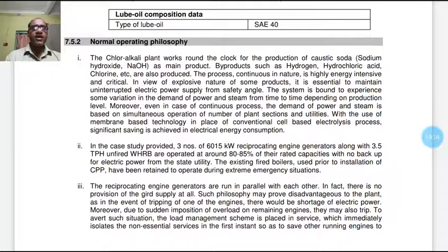The existing fired boiler used prior to installation of CPP has been retained to operate during extreme emergency situations. The reciprocating engine generators are run in parallel to each other. In fact, there is no provision of grid supply at all. Such philosophy may prove disadvantageous to the plant, as in the event of tripping of one engine there would be shortage of electric power. Moreover, due to sudden imposition of overload on the remaining engine, it may also trip.